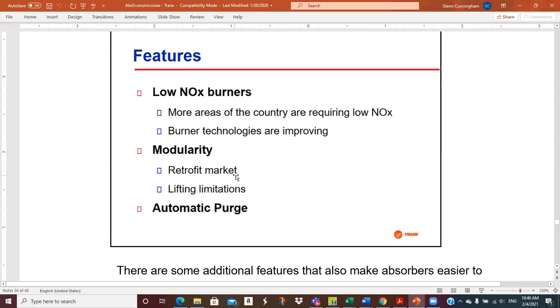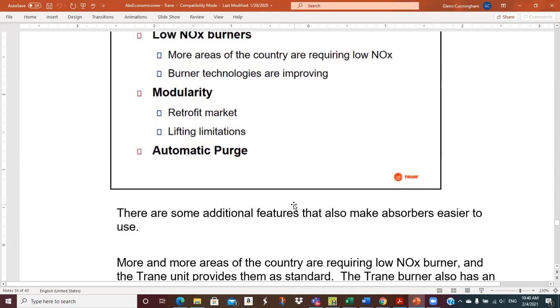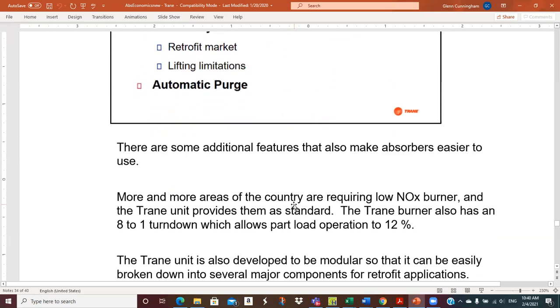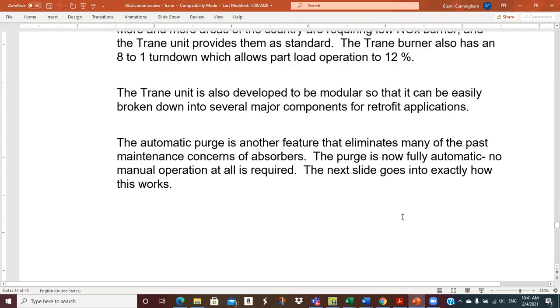Modularity, retrofit market. You can find units of size and they can be taken apart into a couple of pieces and shipped and put back together and all that. So lifting limitations. And automatic purge to get the air out of the system. We mentioned that before. More and more areas of the country requiring low NOx burners, and the Trane unit provides them as standard. Also has an 8-to-1 turn down, which we mentioned before. We're going to move on here.